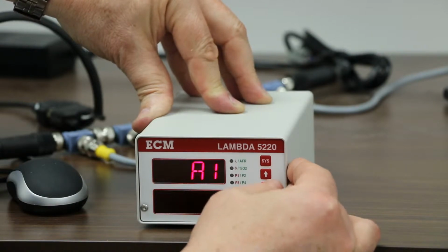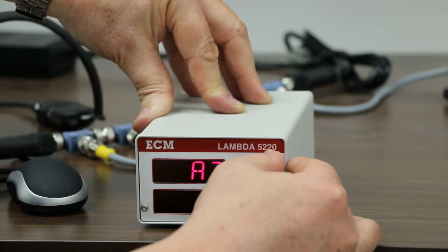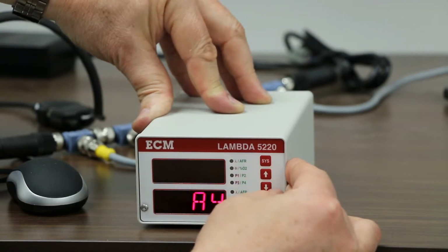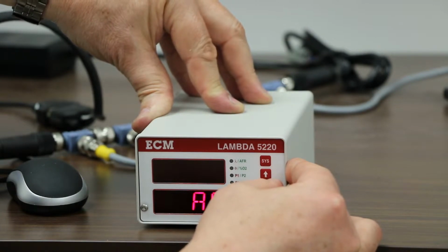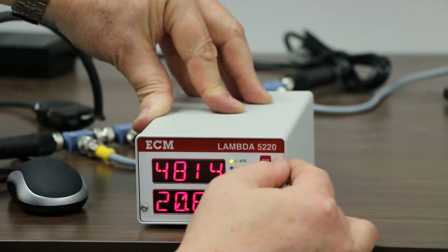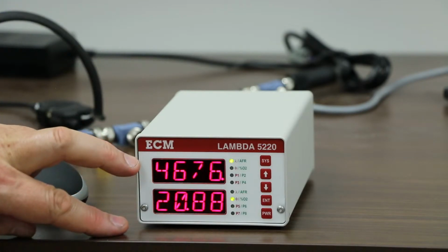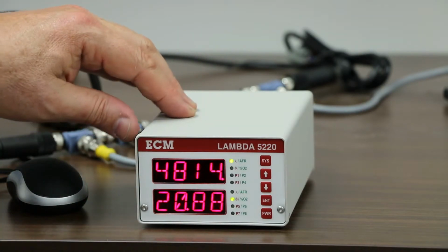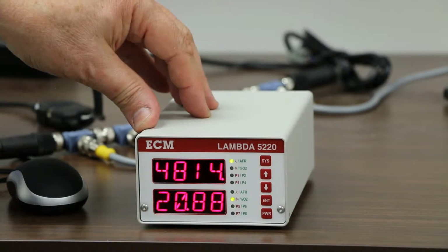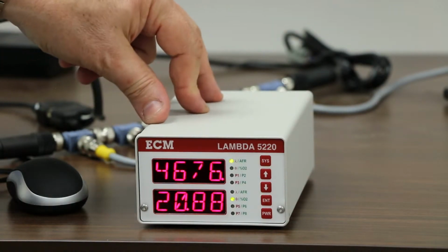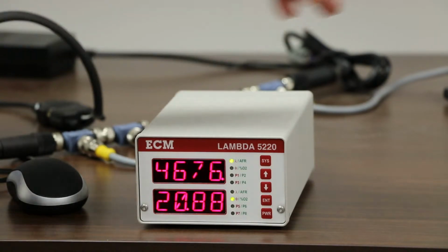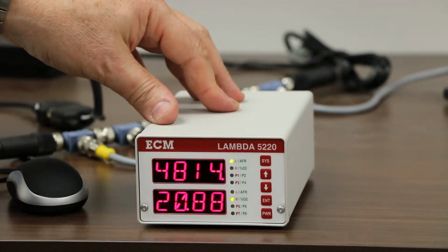And then you do the same for A2, A3, going down here, and you set it up for A4, A5, and A6. So you've now set 2 display parameters and 6 analog, that's a total of 8, plus 2 that are going to come as error codes. Then you do this in your other analyzers.